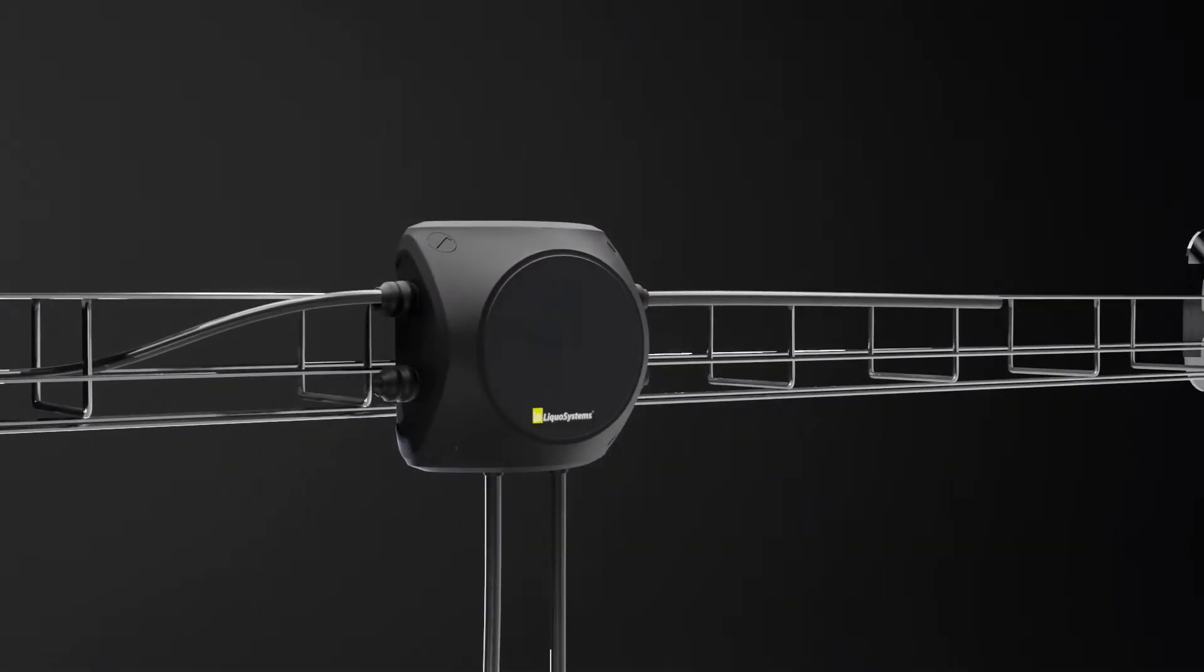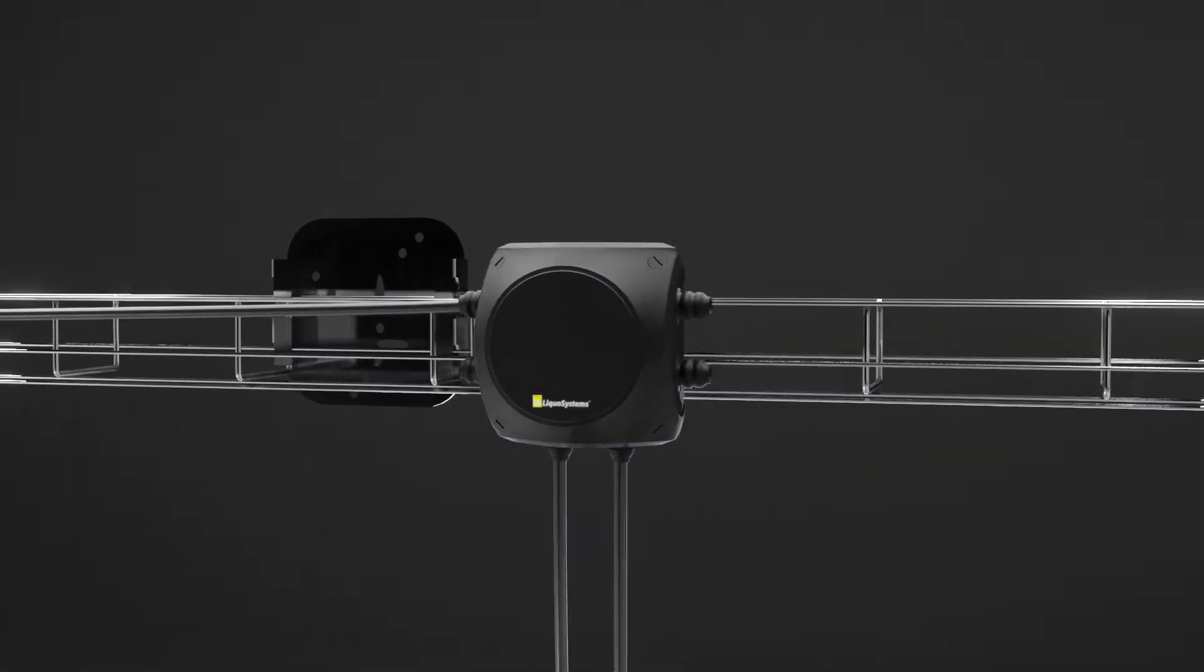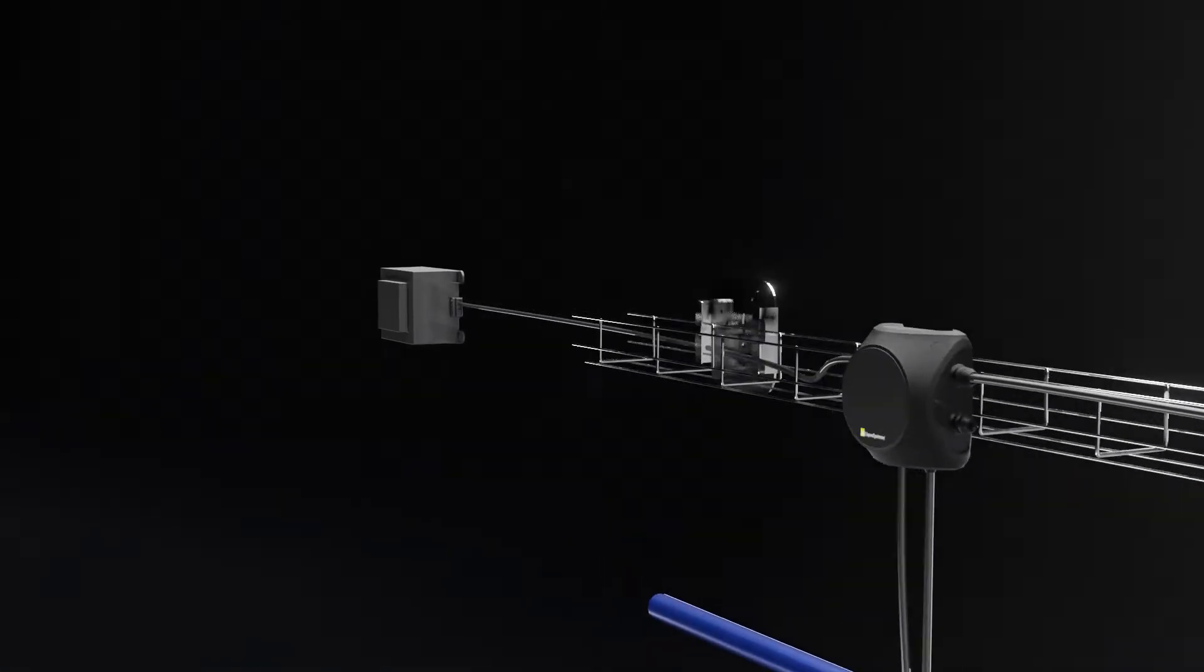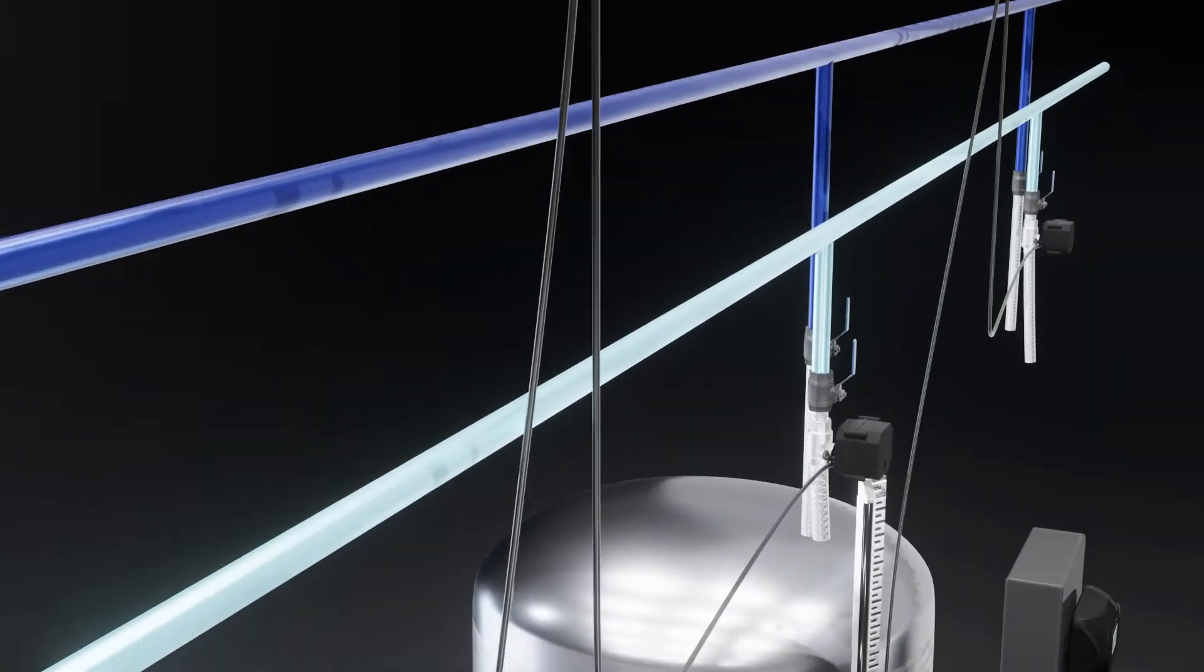If several tanks are being used, the 24V power cable is then connected from one nano box to the next. A 200VA transformer can supply up to 12 tanks with power.